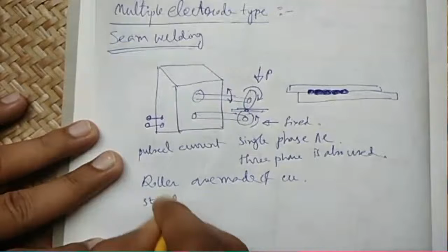These rollers are made of very highly conductive material like copper, and a step down transformer is used as we require low voltage and higher current, as the formula is H equal to I square RT. So I is required to be higher and V is kept lower to avoid any accidents.